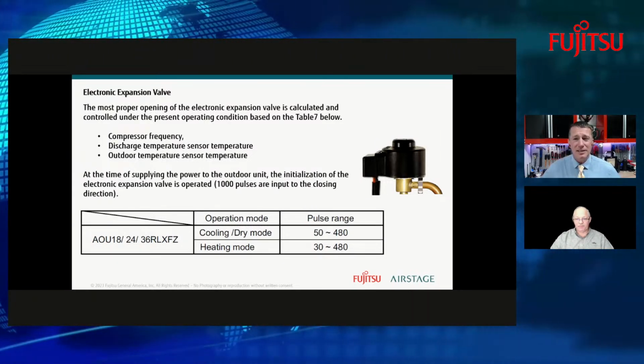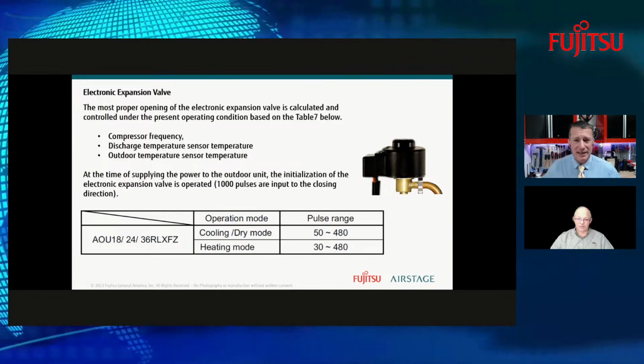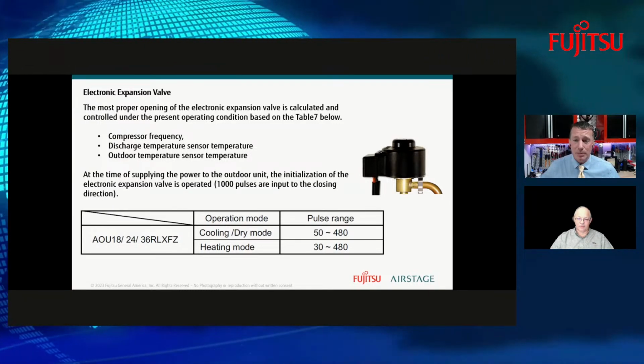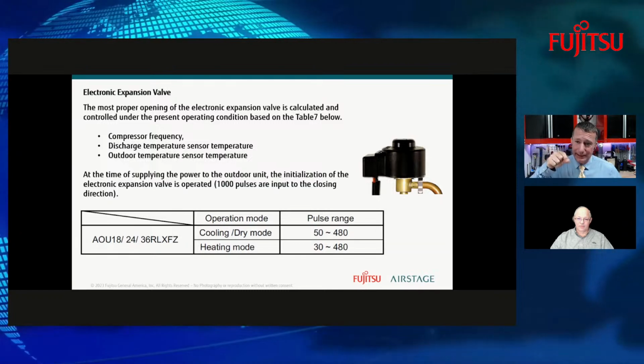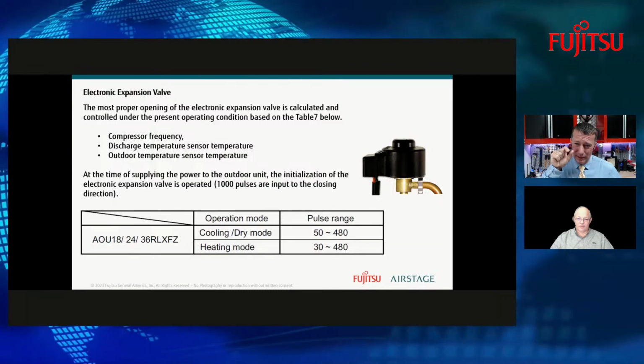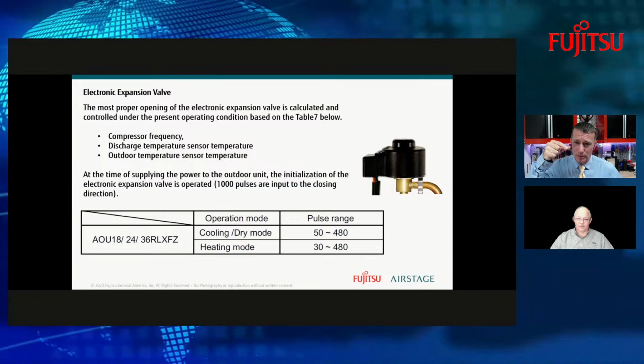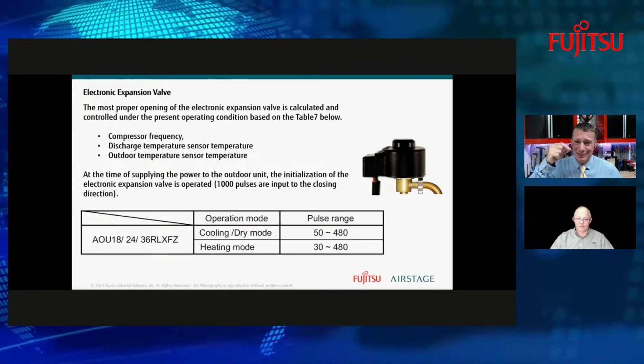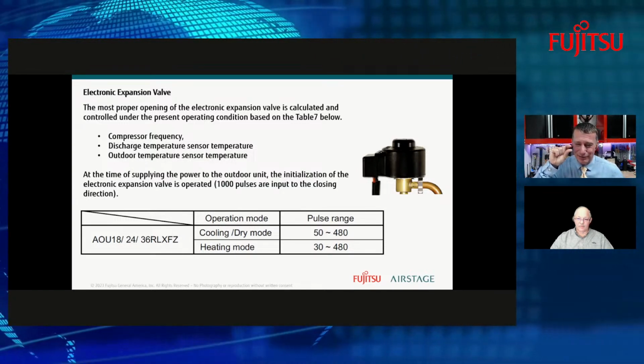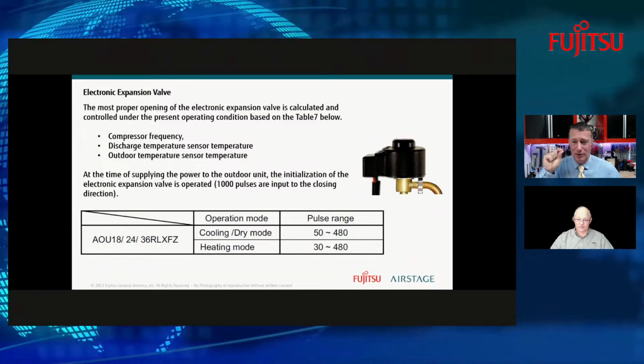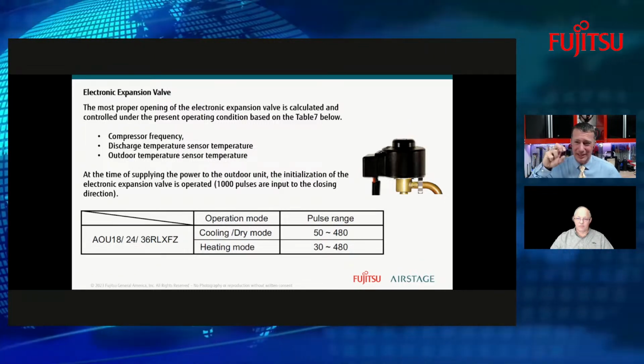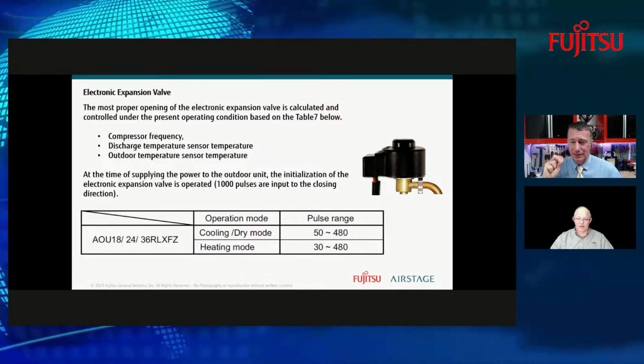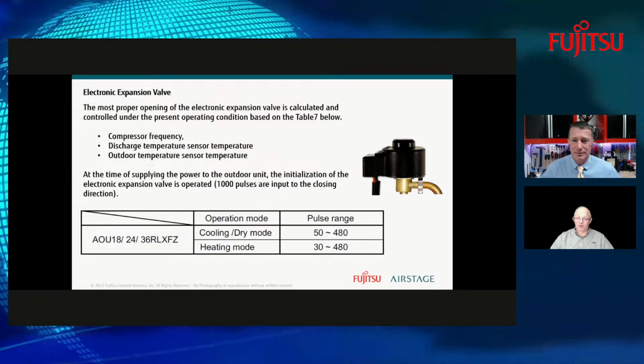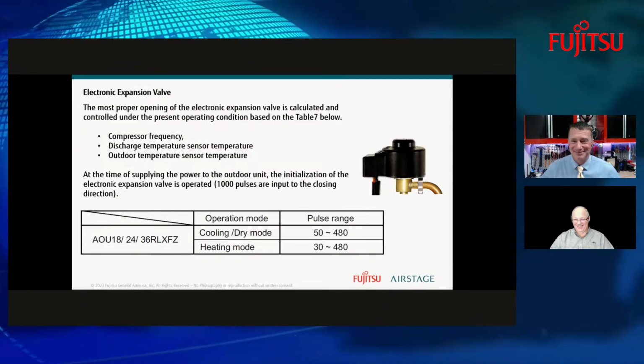Yeah, and I've actually seen that out in the field, not on your brand, but I have seen that before, where in shipping it has not been completely seated down. I've even seen some where it was just partially seated, where the tines were pushing onto the side of the tubing. So it was a 16th of an inch from being seated, and therefore it wouldn't open and close properly. So it's very important just to make sure that it is snapped down into place and seated correctly. We have no way to control truck drivers. Absolutely not.